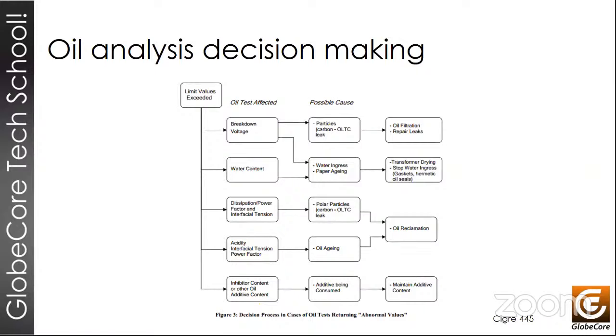On many occasions, corrective maintenance is put aside, and this ends up giving us problems. And the Cigre 445 document presents us with this table, and we're going to work a lot throughout the rest of this presentation based on this table. So the first thing is that once we have done our analysis, we'll be able to see the different elements that are affected within the transformer. For example, we can see breakdown voltage faults. That is a value that can be decreased. We can see increases in the amount of moisture, and we can see problems in the power factor, dissipation factor, and the interfacial tensions. We can see oxidation of the oil and problems in the power factor, or we can see that the transformer has lost the oxidation inhibitor.